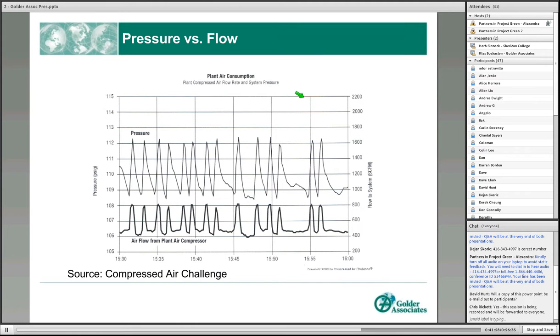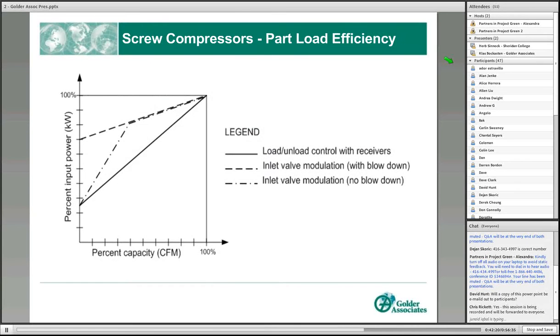And what you see in the system here is basically that the airflow is between 400 and 800 CFM. And a rule of thumb, again, is an efficiently operating system, 4 CFM per horsepower. So that typically indicates to me that you're dealing with about between 100 and 200 horsepower system producing these kinds of flows.